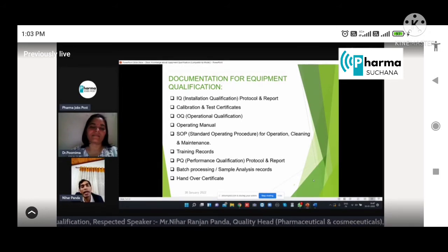Then last is the handover certificate. After completion of DQ, IQ, OQ and PQ, one handover certificate is to be provided, either by the service engineer or by the user department, and also by the QA department. Then the QA department has to check and ensure that all the qualification documents are completed and signed, the batch is processed, the analysis is also completed, and all the results are compliant. Then the equipment handover certificate can be given.